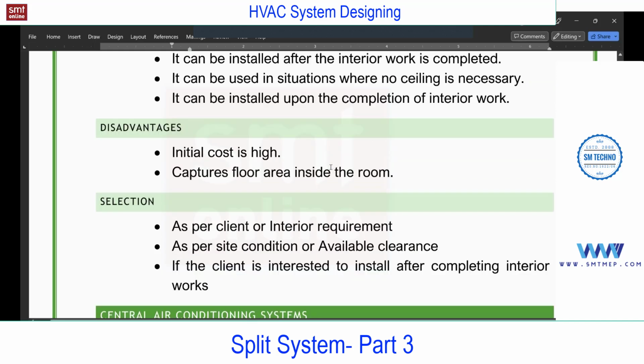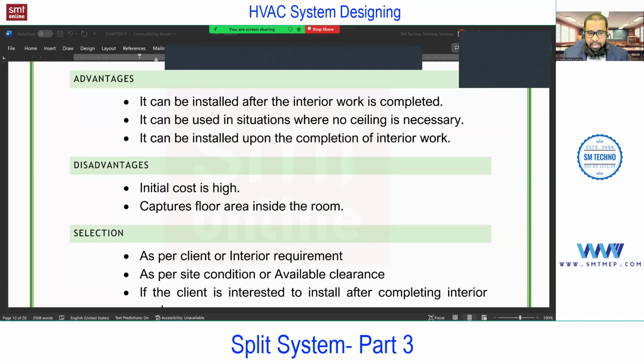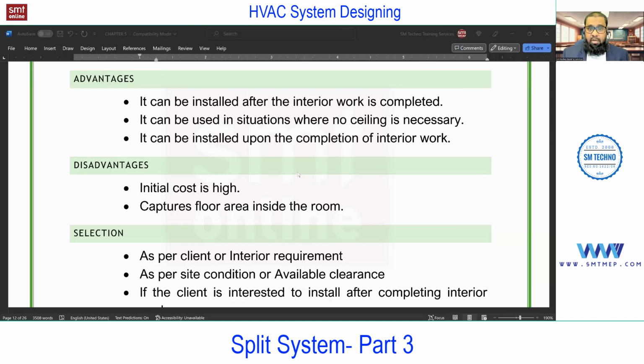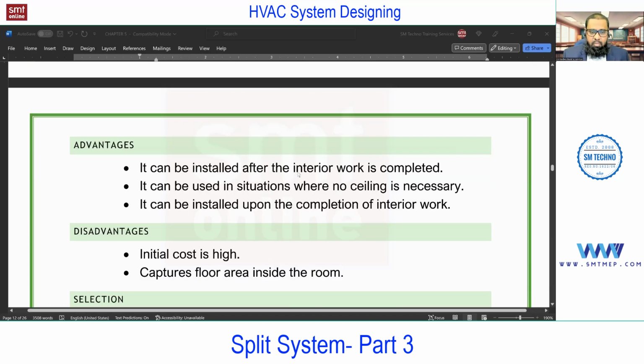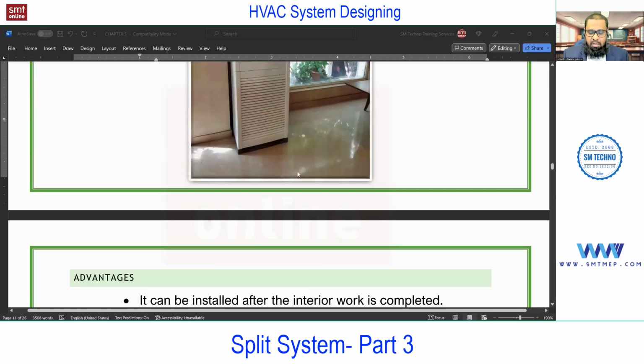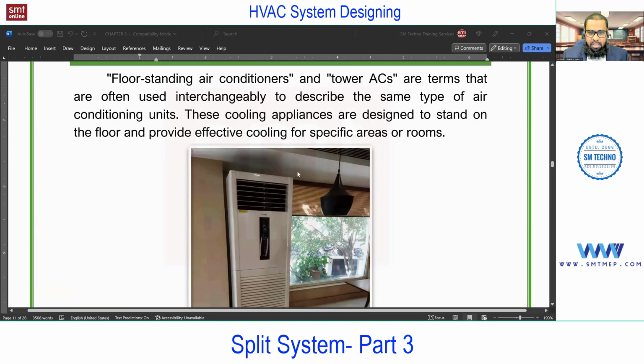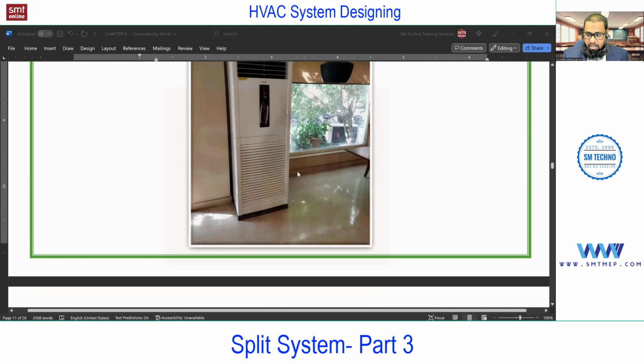Apart from this, you may find other models like ceiling suspended. I'm not talking about cassette. You'll find high wall type in the ceiling suspended also. Or if you talk about cassette, what I explained is the four-way. You may find two-way or one-way cassettes also. Different models are available in FCUs with the split system. Apart from this, you may find a small floor mounted unit, not commonly used. The list of models you may find in different catalogs, but most commonly in actual practice it is high wall, cassette, and if required, freestanding in the split system. So this is about the split air conditioning system.